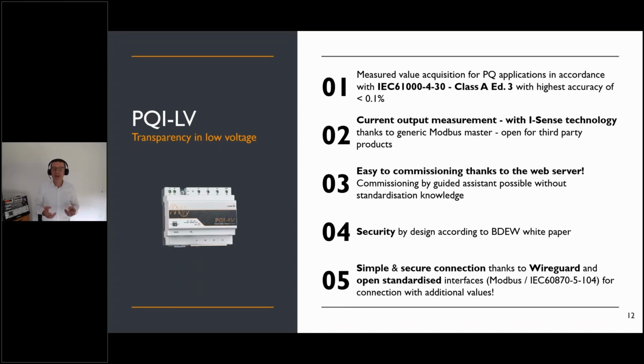We have a Modbus master inside, and we are open for third-party products, so it's possible to transfer data, for example from intelligent feeders, into the PQI-LV. With the PQI-LV you have a data logger inside the substation, as well as an RTU, a real-time unit, which brings the data via different protocols to your SCADA system, or also in parallel into our software solution WebPQ.